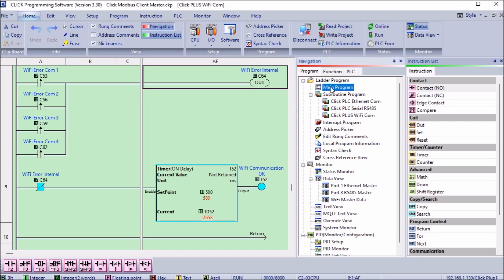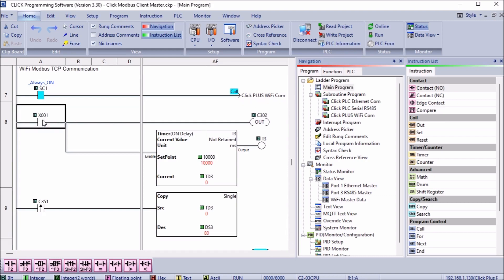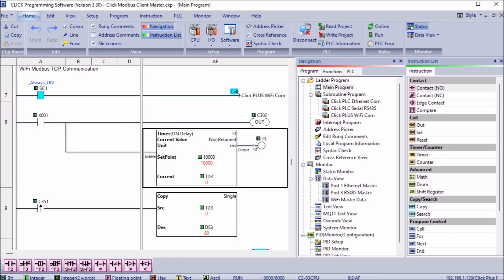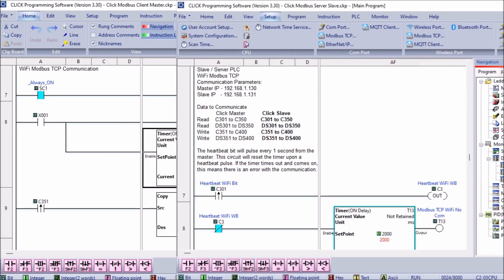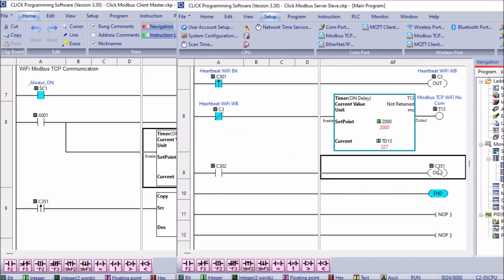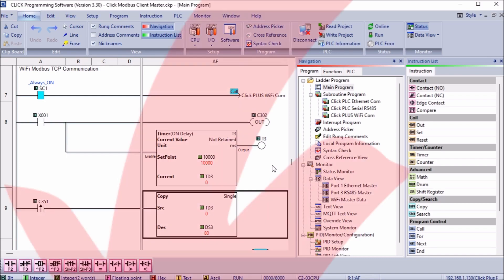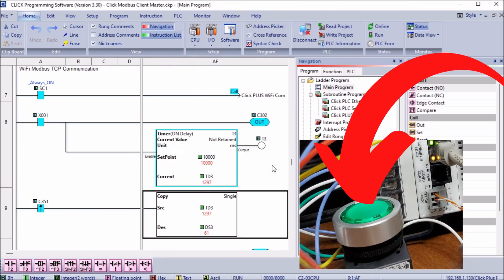Returning to the main ladder logic of our click client PLC, we will implement some code to determine the throughput of our communications. When input X001 from our push button switches on, this will turn on bit C302 and start a timer. Our remote click server will have the following code. This will read C302 and set C351. When bit C351 is read from the click client PLC, the value in the timer is then copied to DS3. DS3 will then contain the throughput value in milliseconds.